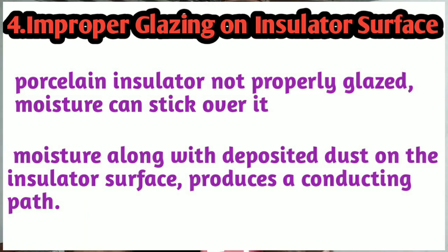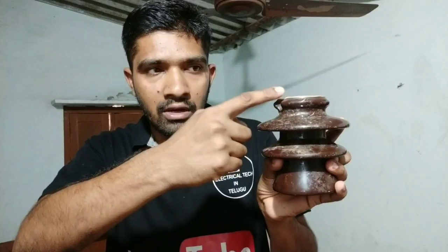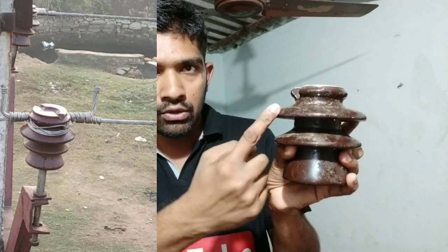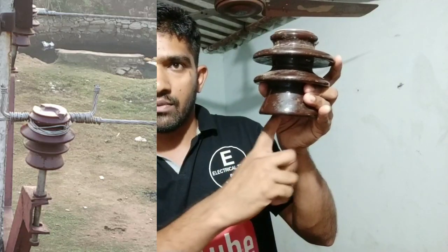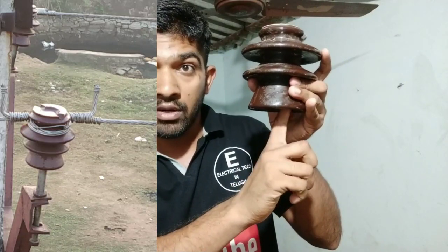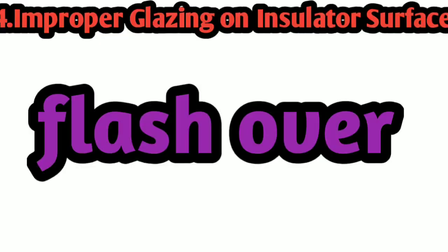There is a conducting path formed on the insulator surface. When there is a conducting path on the overhead line with current carrying, there is leakage. Along the steel rod arrangement, there can be a flashover. When there is a flashover, there is an insulator fail.